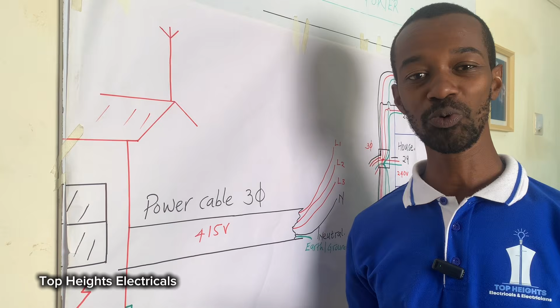My top boss, we discovered one important thing about this setup: the earthing is compromised. Instead of each unit having its own earthing, an earth pit and earth rod, we found there was only one earthing system, located very far away from these units.